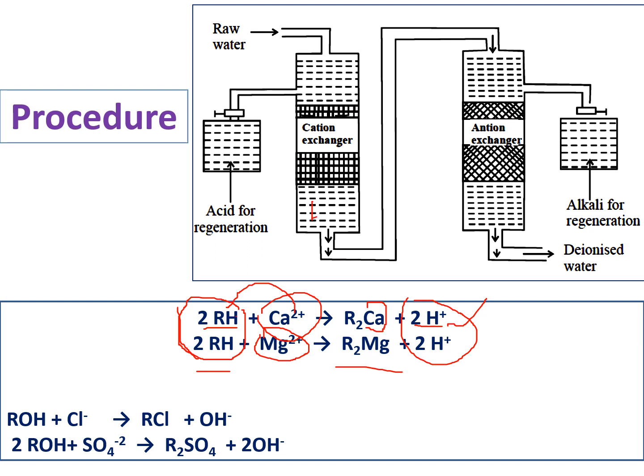This water is then passed to the next tank. Cl⁻ or other anions are replaced by OH⁻ ions, forming RCl, and OH⁻ ions are released. H⁺ ions and OH⁻ ions combine to form water molecules. Over time, the cation exchange resin converts to R₂Ca or R₂Mg, and the anion exchange resin (ROH) converts to RCl or R₂SO₄. This is called exhaustion.